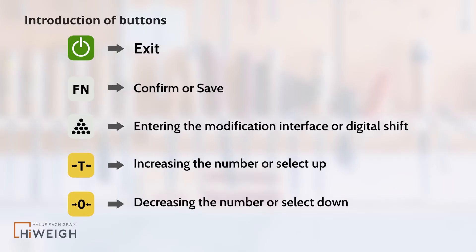When modifying parameters: the power on button functions as exit; the function button functions as confirm or save; the accumulation button is for entering the modification interface or digital shift; the tare button is for increasing the number or selecting up; and the zero button is for decreasing the number or selecting down.